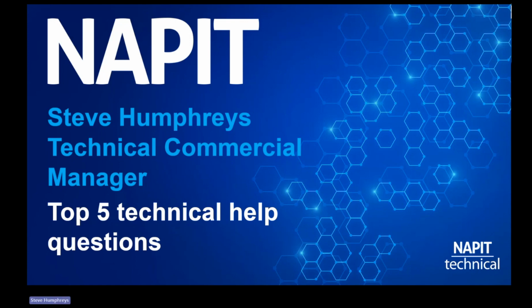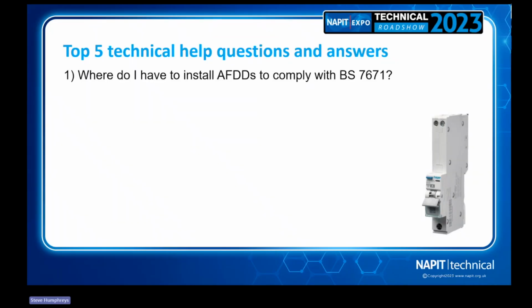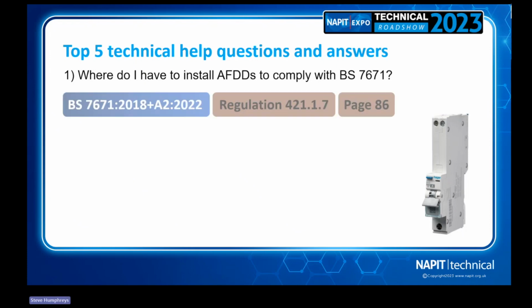So first one: a question we get quite a lot is to do with particular devices in consumer units. Not uncommon to have these kind of questions because we're fitting consumer units with new and wonderful things all the time now. So this one says, where do I have to install AFDDs, arc fault detection devices, to comply with the wiring regulations BS 7671? What we will always do when we're giving our members information or running through any technical help, or anytime me or Frank present anything, we always want to base it on what the wiring regulations say. We don't want to give spurious opinion, because if you've got 100 sparks in the room, they'll all give you 100 different answers.